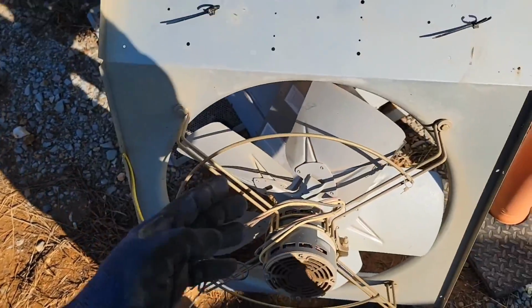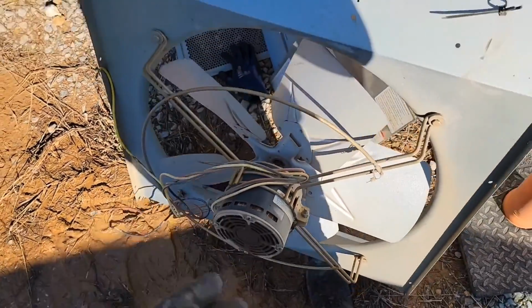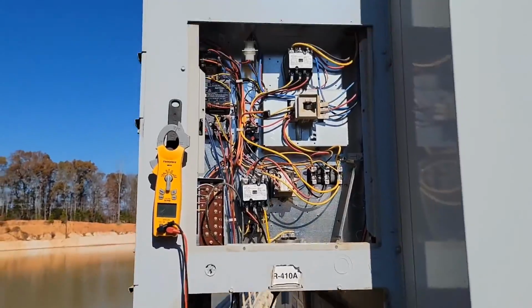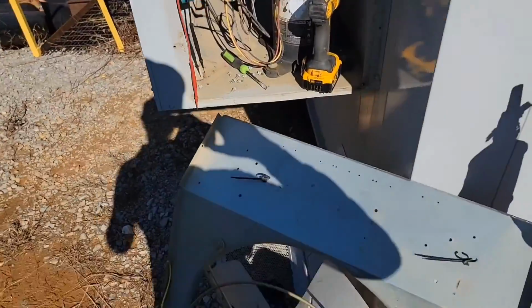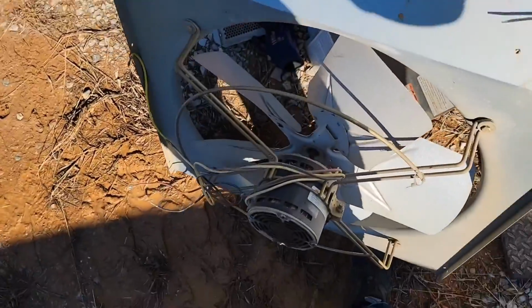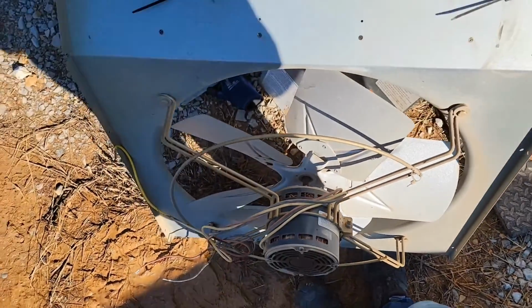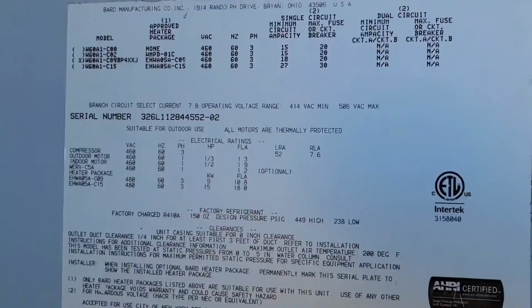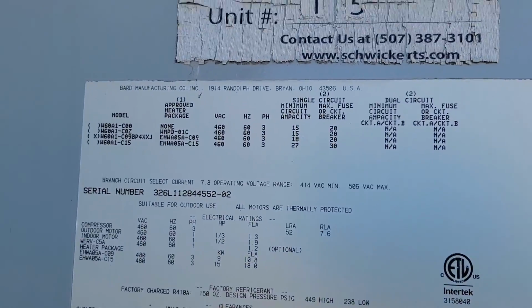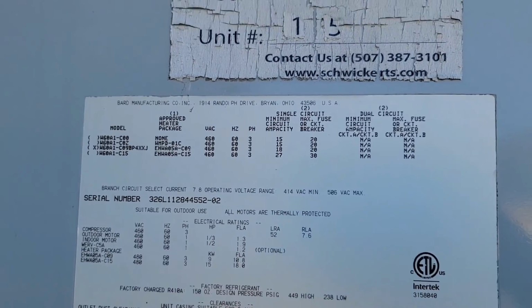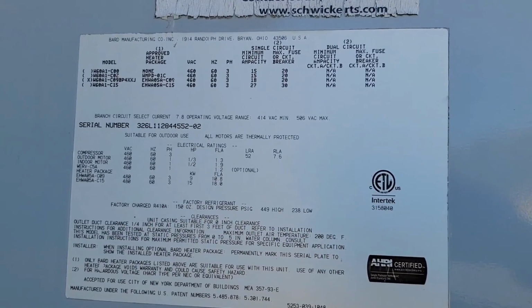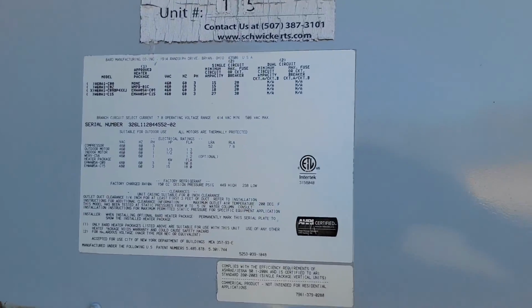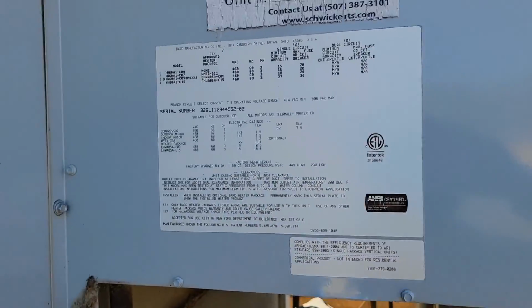So we got our fan motor. We're gonna take it to the shop, put a new fan motor on. Actually, I'm sorry, I'm gonna order a fan motor because I do not have anything like this. So I need to get the model serial number and order a 460 volt single phase fan. Here is the model and serial number of this equipment. So I will utilize this to get the new motor. Or if I got a part number on the motor, I can use that.